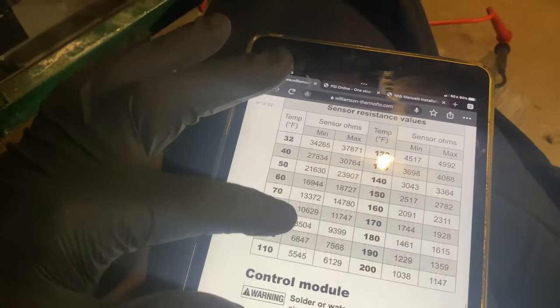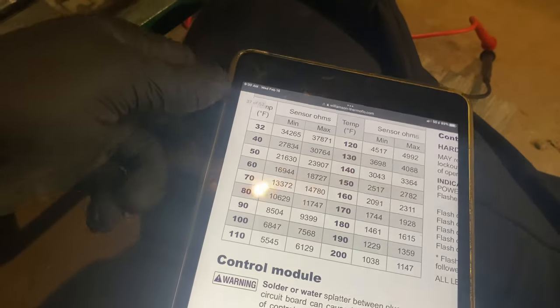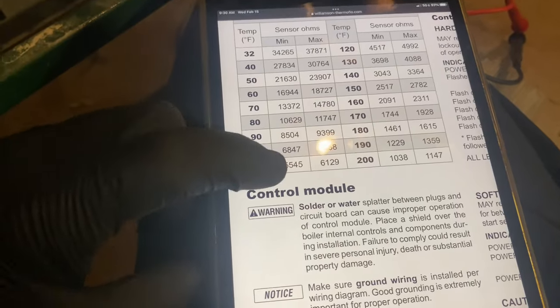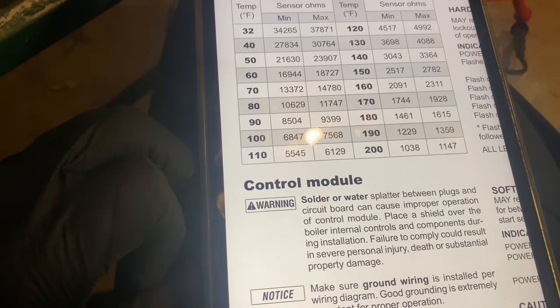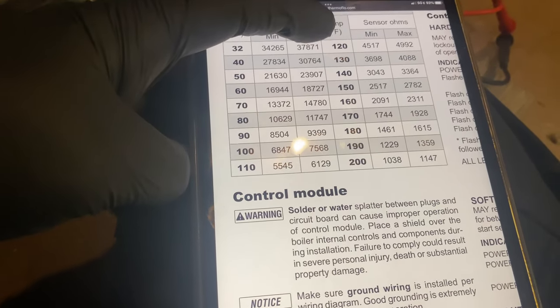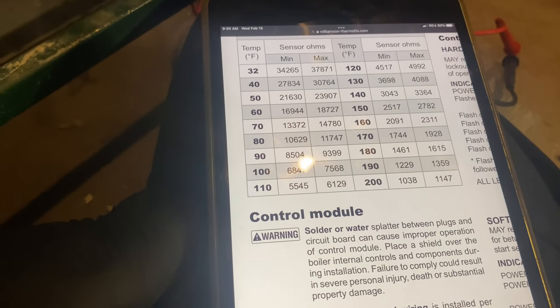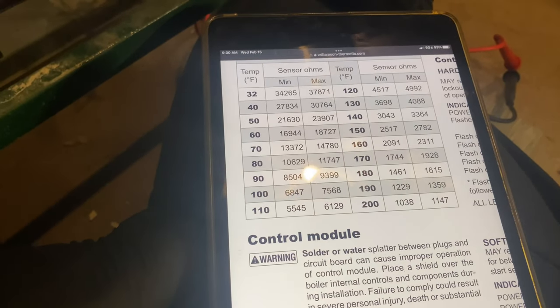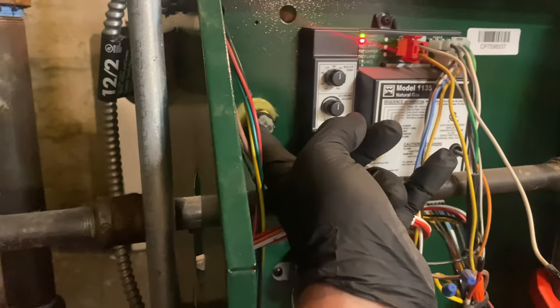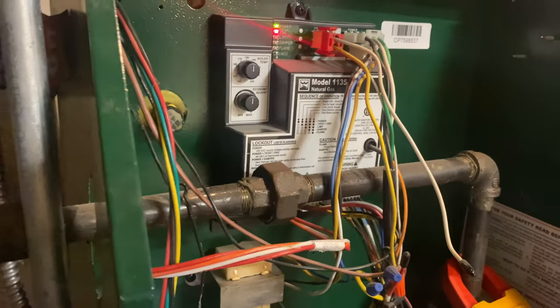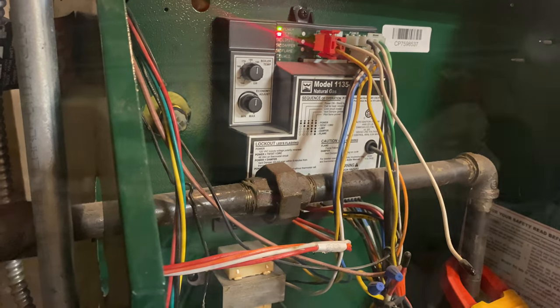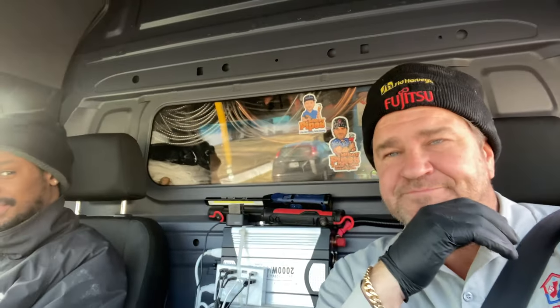So 5347, if we go to our chart here, it thinks it's 110 degrees, between 110 and 120, okay? So not only do we have an issue with the temperature sensor, we also have an issue with the control module. See, double whammy.